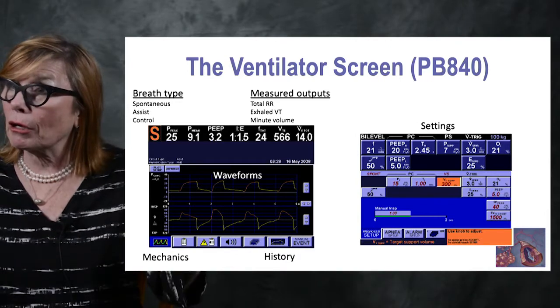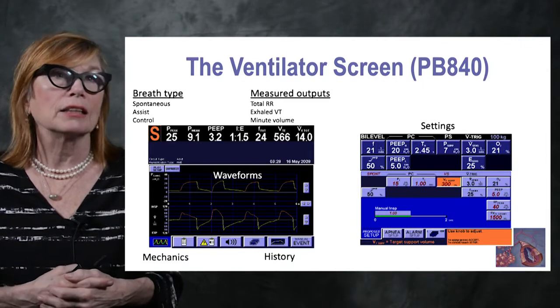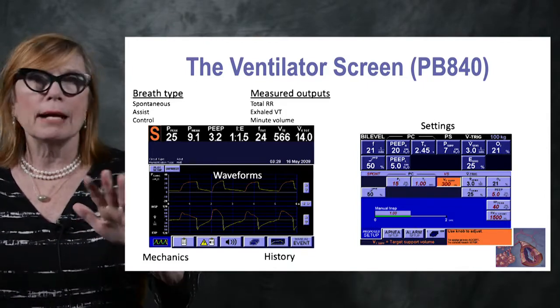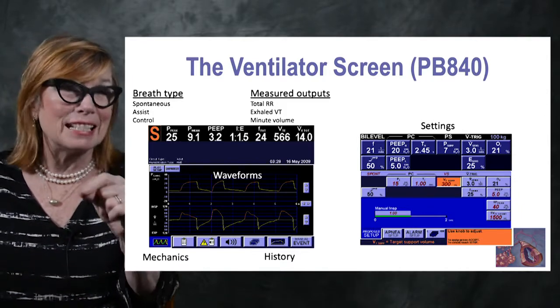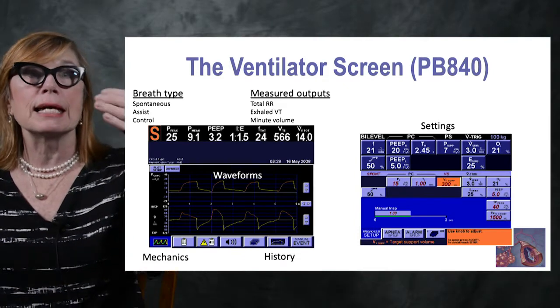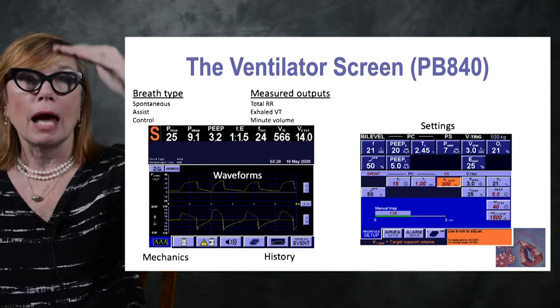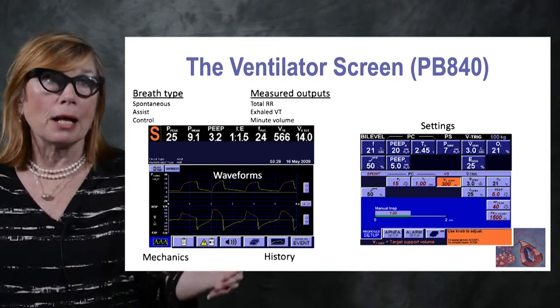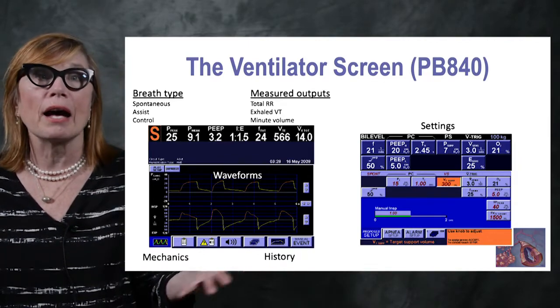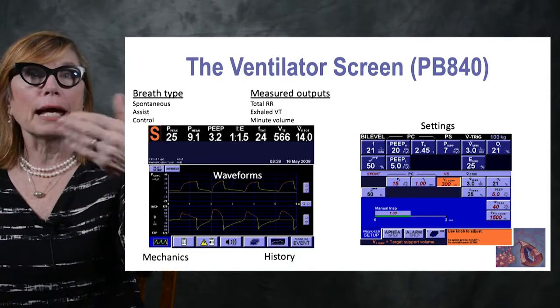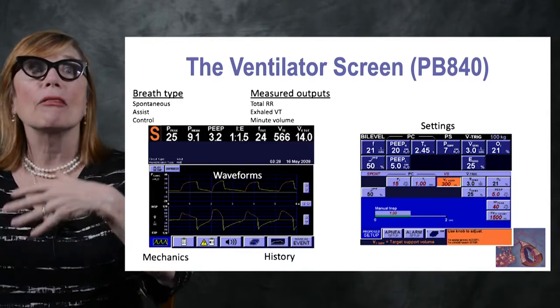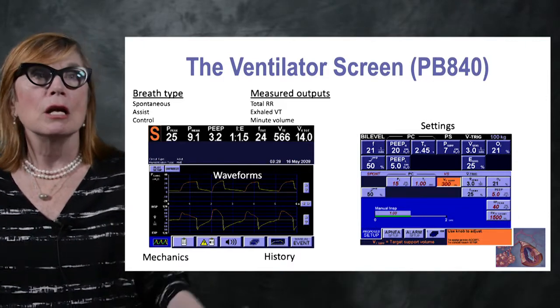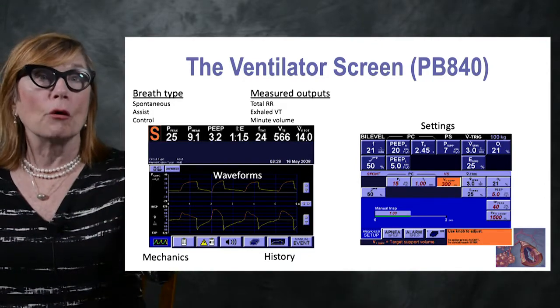We can also look at patient history, mechanics, and waveforms showing the dynamics of gas flow to an endpoint of either pressure or volume. On the lower part of the console you see the settings — here the patient is on bi-level, meaning high pressure/high time and low pressure/low time. Settings show frequency, high PEEP (20) and low PEEP (5), inspiratory time (2.45 of the cycle), pressure support on spontaneous breaths, flow, sensitivity, and oxygen concentration.